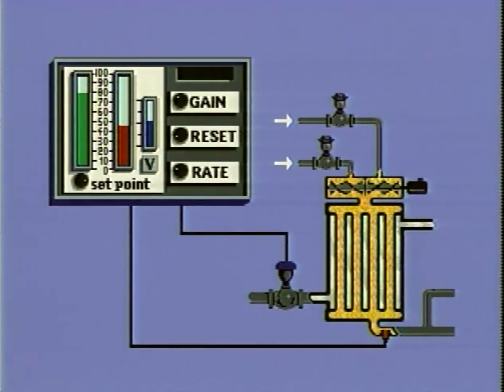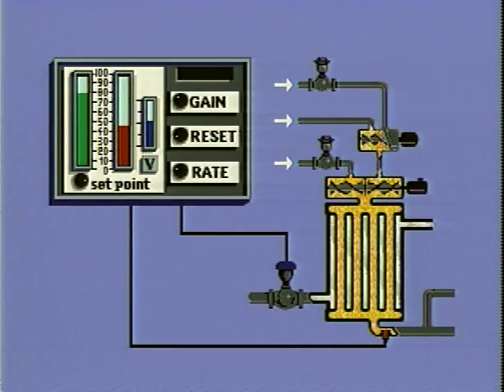An additional pipeline was installed that intersected with the line that formerly carried component A into the mixer and heat exchanger. The two ingredients were then mixed together in the pipeline to form component A. The only problem was that the plant had to somehow make sure that twice as much of the second ingredient always flowed into the pipe's intersection. A ratio controller was used to make sure that happened.